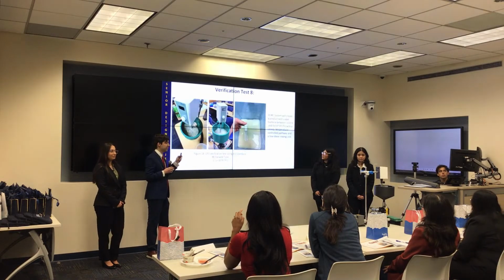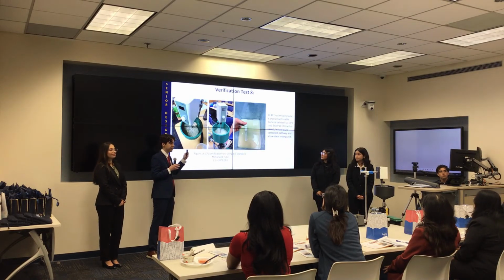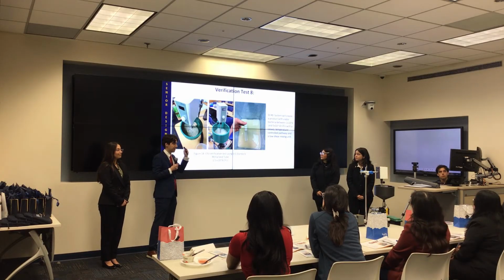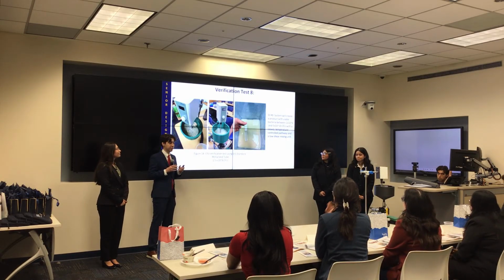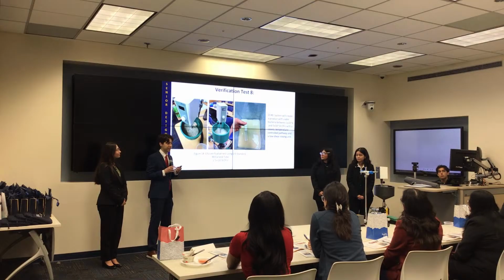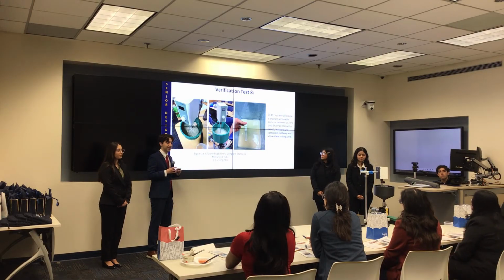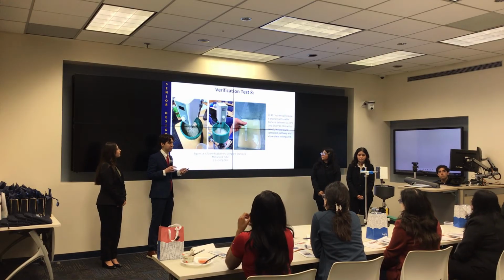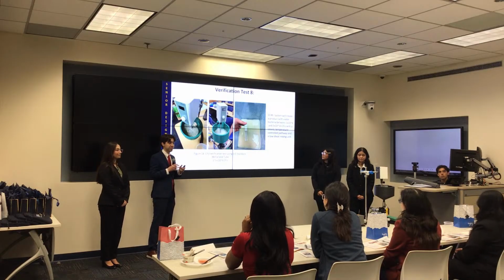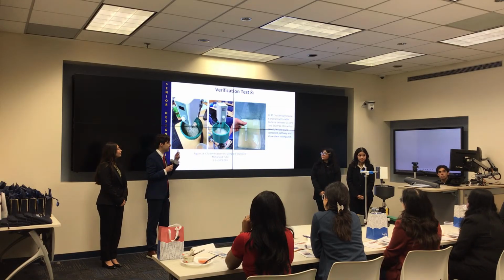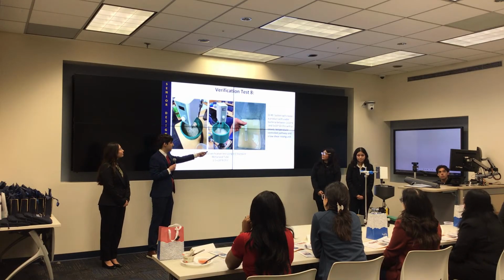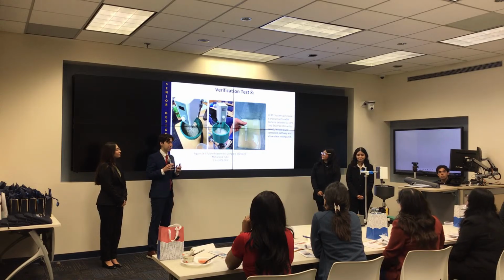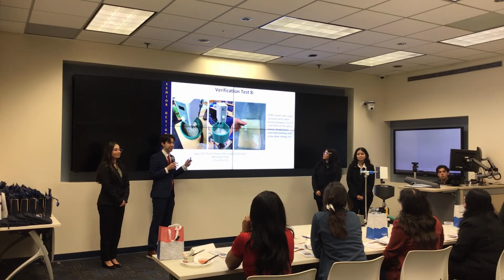The next and most important test you can see right here, which is the CFU test to measure bacterial viability. If our method produces product with significantly lower bacterial viability than previous methods, then there's no point in creating this product at all. So this test was extremely important. In order to conduct it, we created a simulated stool sample made from yeast and water and then passed it through our system. We then compared its turbidity to a standard tube, you can see right there, which estimates to about 1.5 times 10 to the 8 CFU.